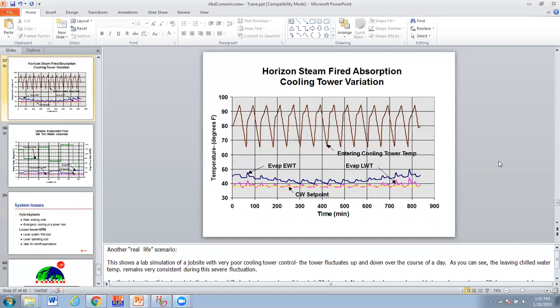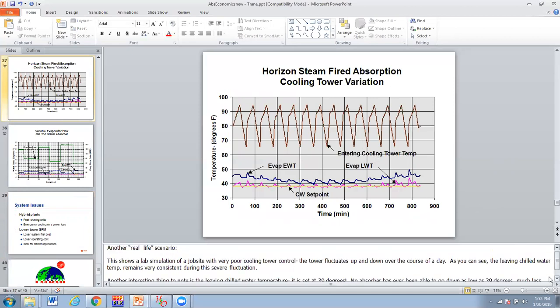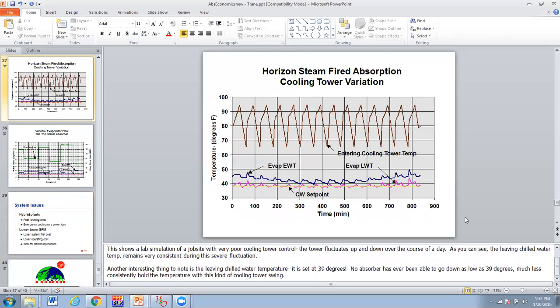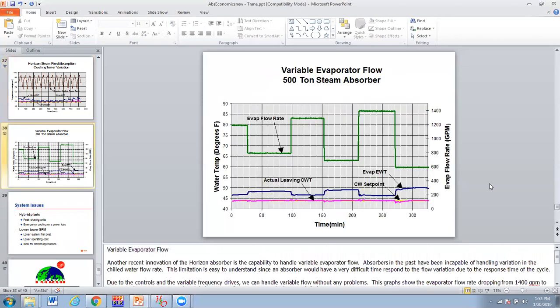you can read over that. Okay, here's one. They call this a real life scenario where condenser water temperature kind of seesaws up and down. And basically you can see that the chill water temperature set point is the yellow, and the magenta one is the actual. I mean, it got a little bit of fluctuation, but it's not too bad. And also notice that it's set on 39 degrees, which is pretty darn low for an absorber. So that's pretty good.